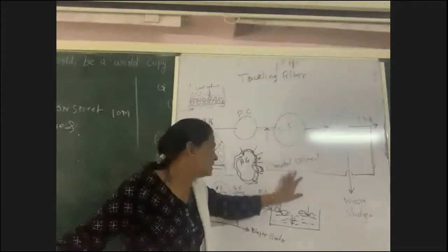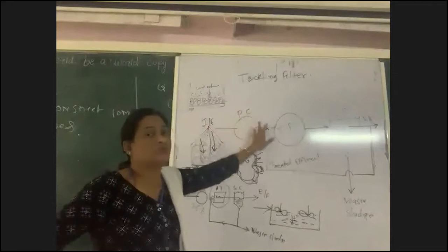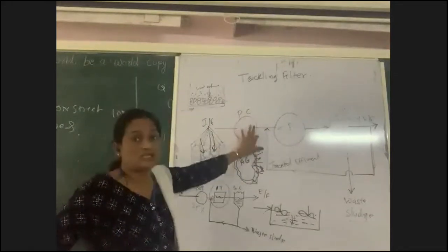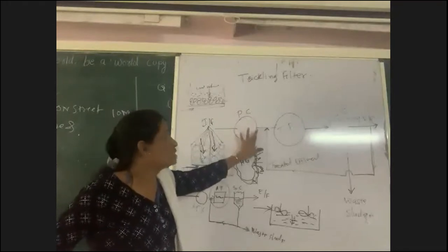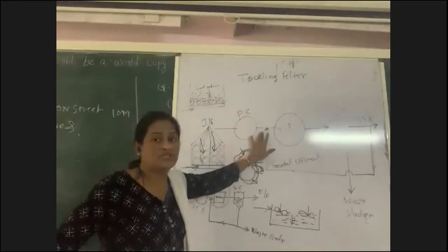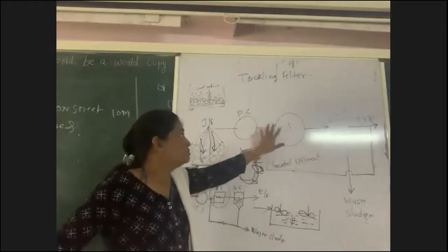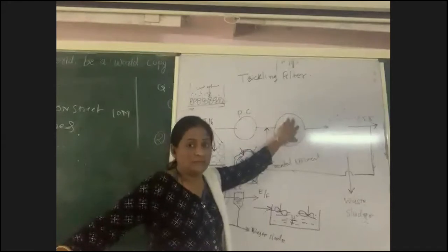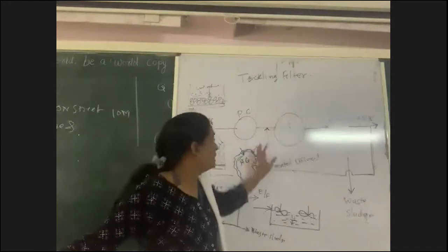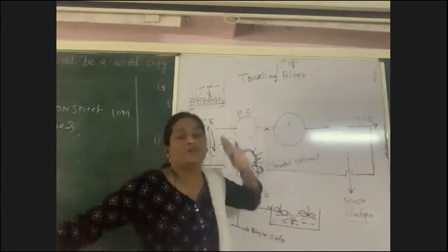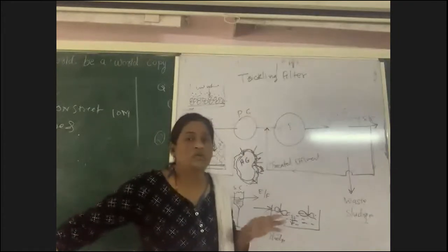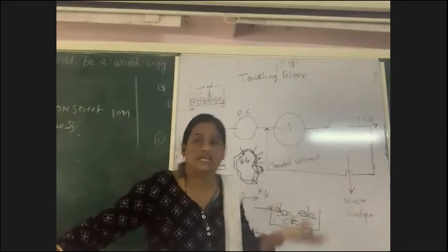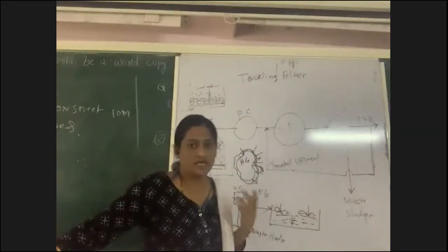Now how to decide that? As per the quantity and quality of incoming sewage. If the concentration of BOD or suspended solids in the incoming sewage is very high, then in that case there is a possibility that your trickling filter will get blocked. In that case you need to dilute some quantity, and for dilution purpose you cannot go for borewell water or river water because you need extra energy to expend for that.